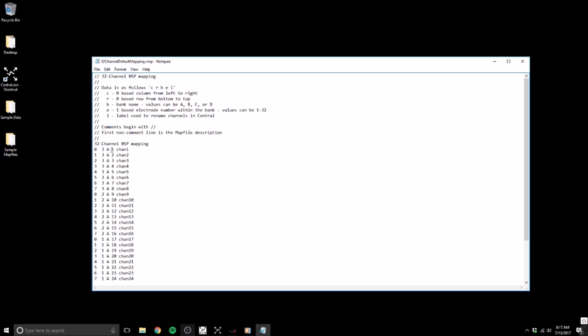The next 2 columns show channel number. BlackRock products operate in banks of 32 channels, each bank being labeled with a letter. Thus, A31 represents channel 31, A32 represents channel 32, and B1 represents channel 33. These channels refer to the physical pin on our recording system, and these physical pins are associated with software channels. If you ever need to see this in more detail in Central, it can be found in the hardware configuration under Channel Properties. The final column is the channel label.